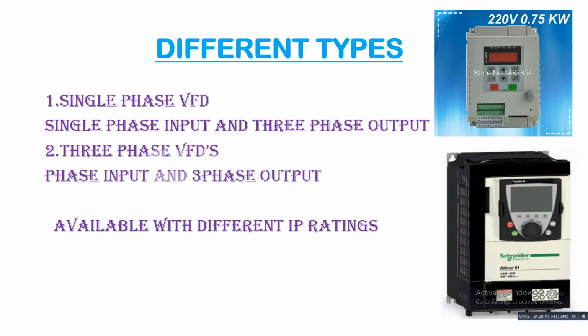Now we'll see what types of VFDs are available. There are two major types. One is the single phase VFD, which is available with single phase input and three phase output. Another is three phase input and three phase output. It is also available in different IP ratings, normally IP20, IP54 and IP65, so you have to choose your VFD rating as per your requirement or application.